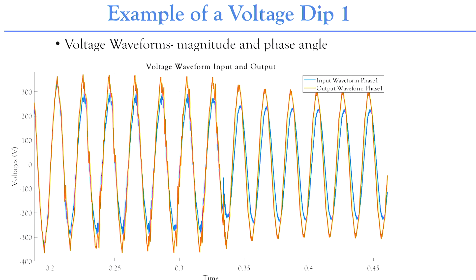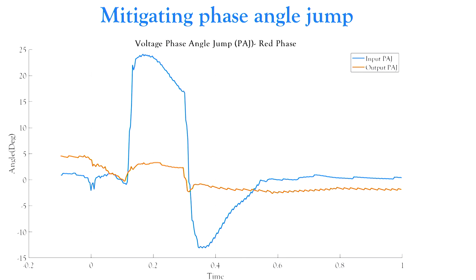This one is to demonstrate phase angle. One would regard phase angle to be fixed, and this is from the grid during a fault. A phasor, for those familiar with the concept, can jump up and down. In other words, they are not perfectly displaced at 120 degrees and not perfectly stable, and that alone can make equipment stop, not only the change in magnitude.